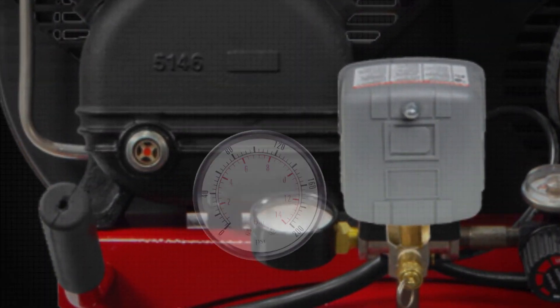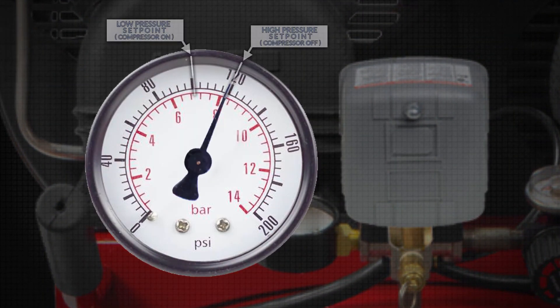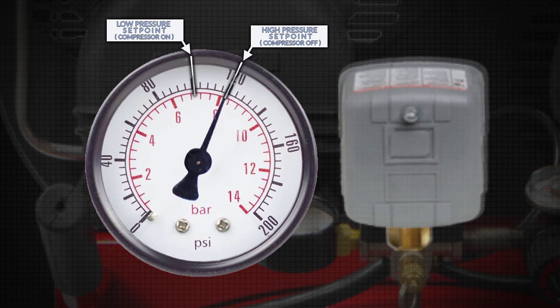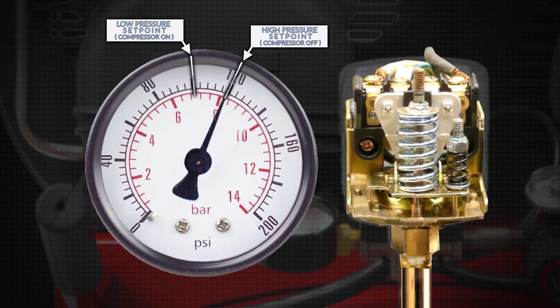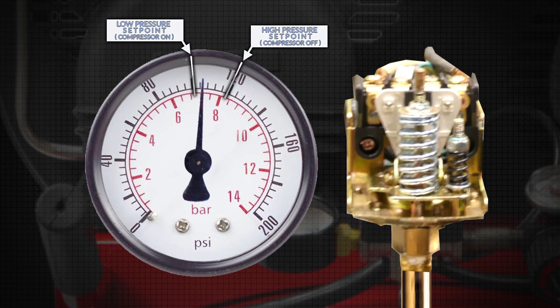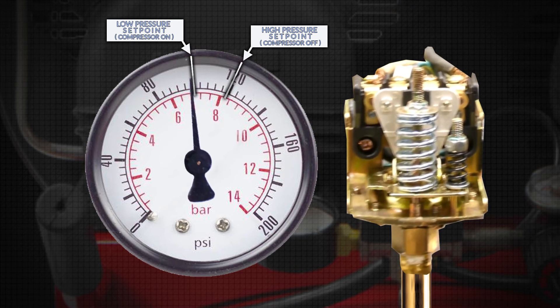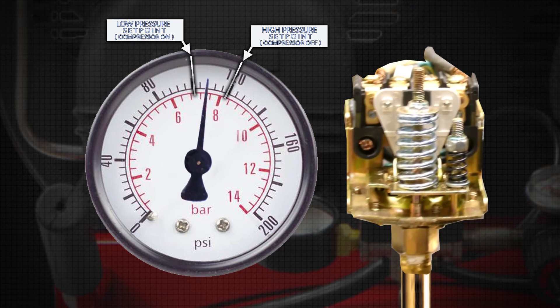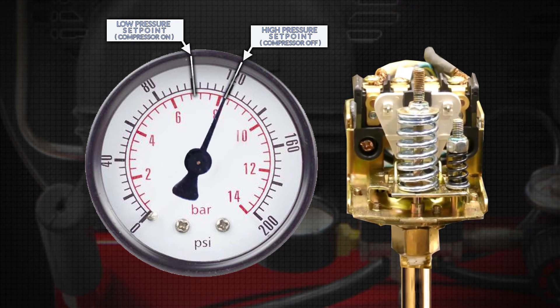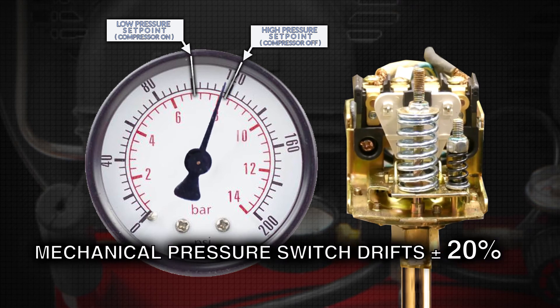An air compressor pressure band gap is the area between the low and high pressure set points. In most air compressors, the set points are set with a mechanical switch that relies on spring tension that is imprecise, unrepeatable, and subject to environmental humidity, vibrations, and pressure. Due to mechanical wear together with fluctuating environmental conditions, both the low and high set points drift over time, with estimates as high as 20% annually.